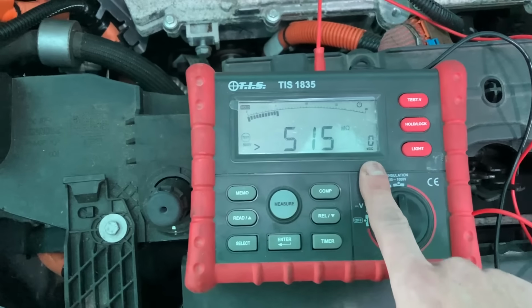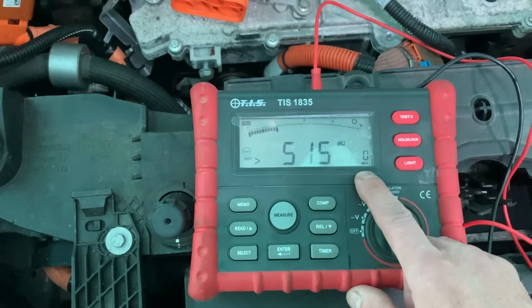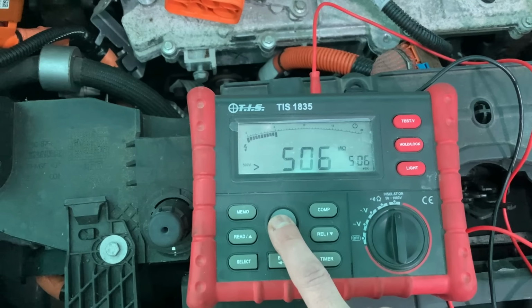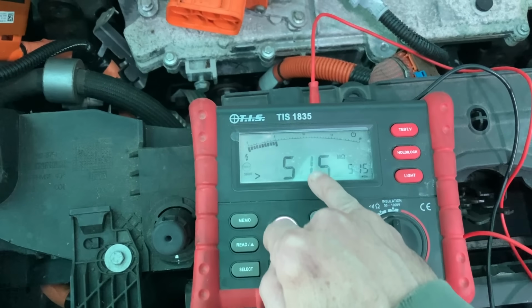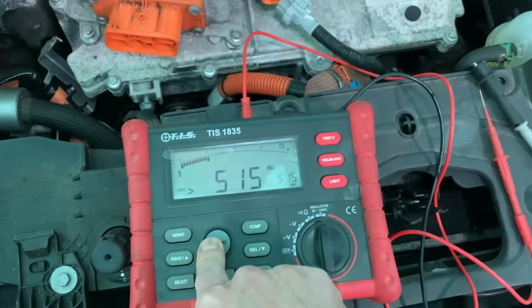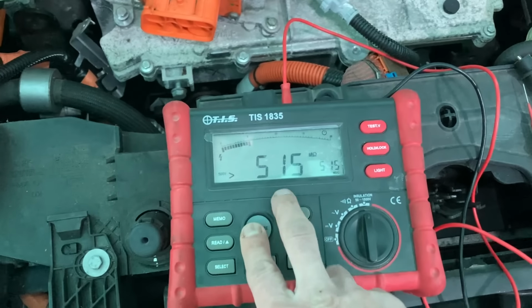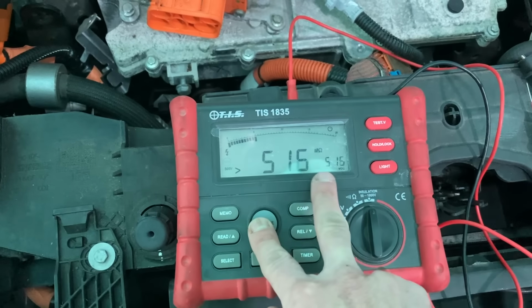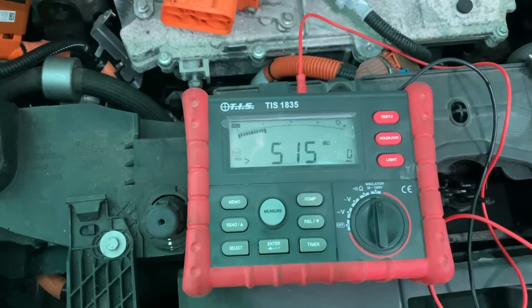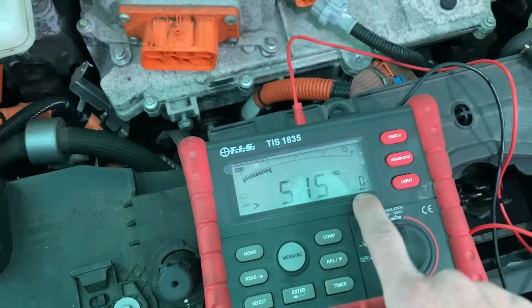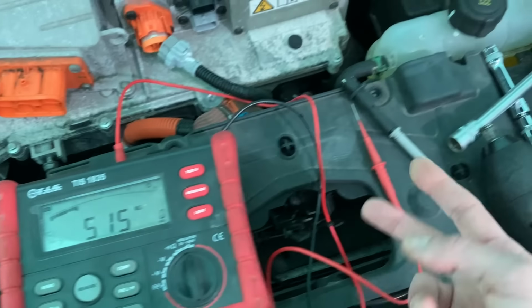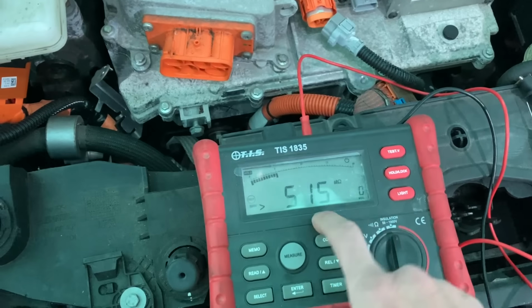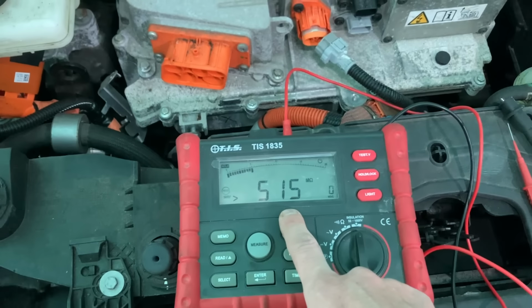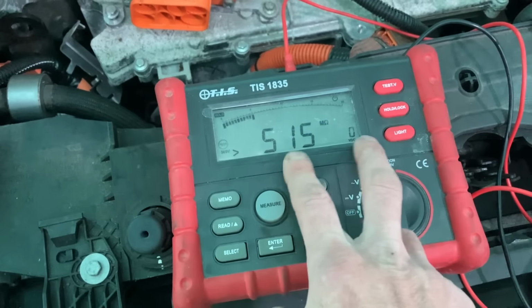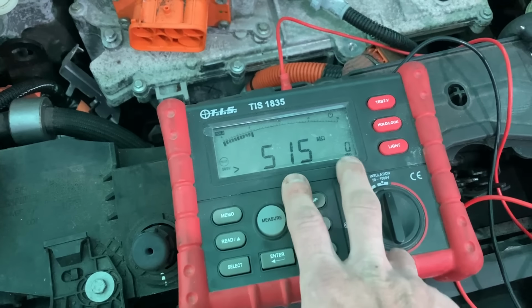One thing I don't like about this meter is it doesn't show you the voltage it was able to achieve - you can only see that while pressing the button. The other thing I don't like is these two: this flashes to tell us we're doing a test, we've got 500 volts there, and these two always show the same, which I don't particularly like, because it doesn't give you that confidence - it looks a bit wrong because there are two different readings. This is the voltage the meter is able to generate on those leads, and this is the actual resistance. Sorry, getting a lot of glare there. So it just feels a little weird that they show the same.